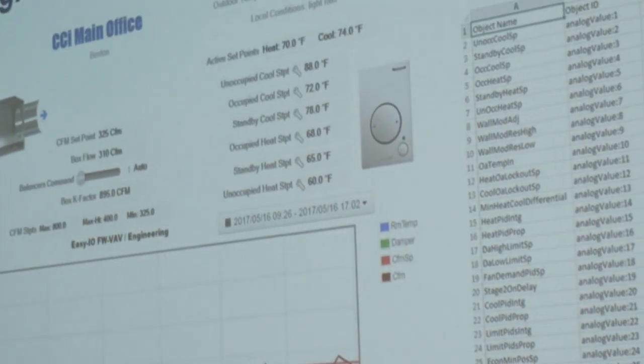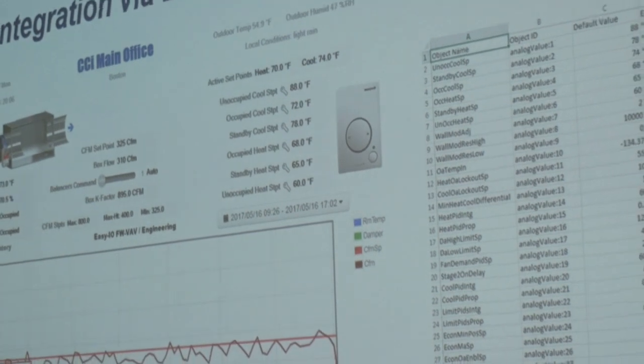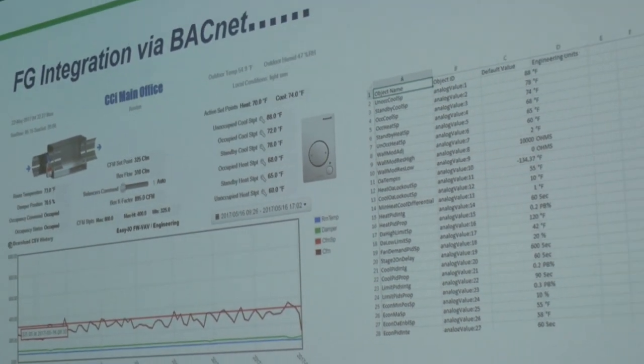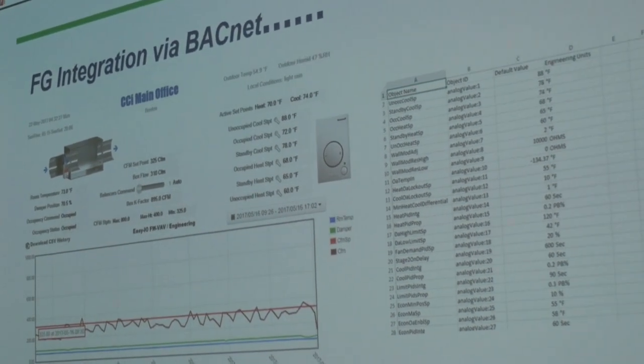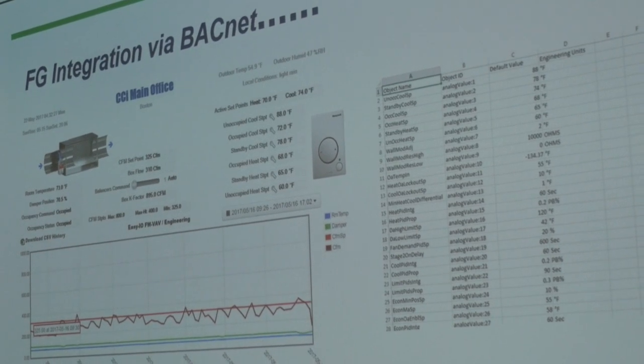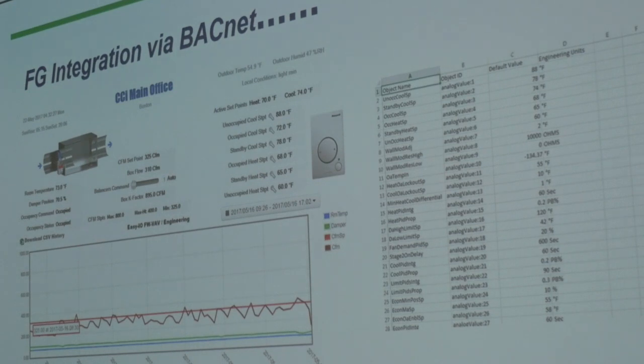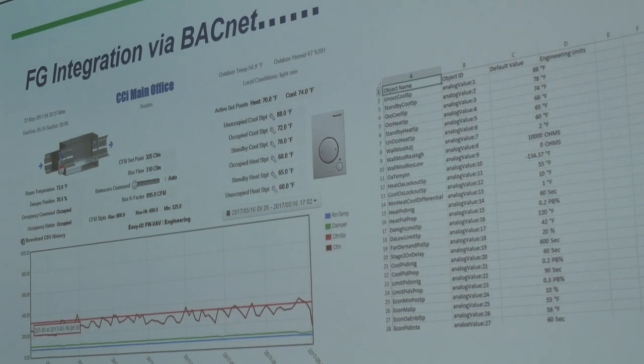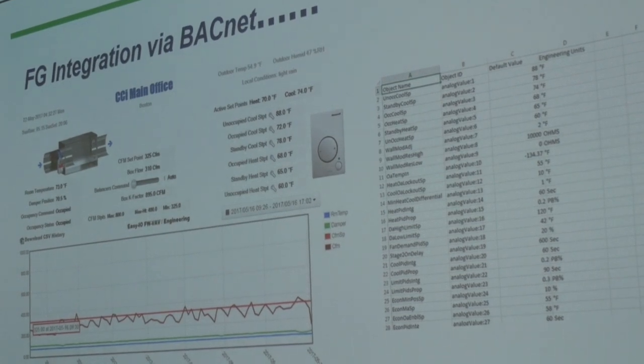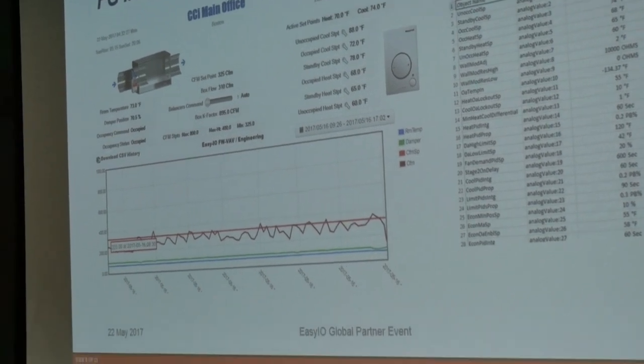This is live, we have ours integrated. We've been thoroughly testing it at our office. And our office is a VVT zoning system, so the duct static is all over the place. That is the ideal test ground for this application, because we built a special kit, a special PID. And the PID is designed so that it limits actuator hunting, right? It's the worst thing for a VAV box for the actuator to constantly be on the move.